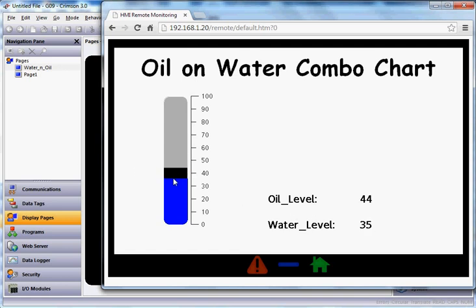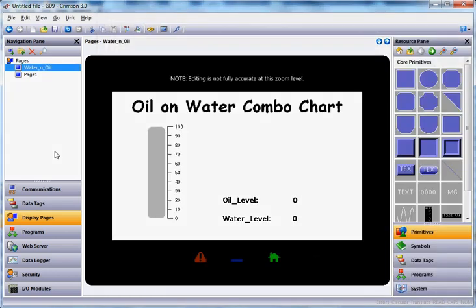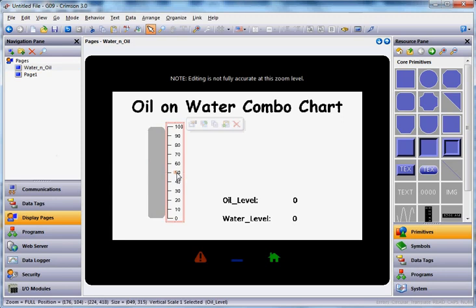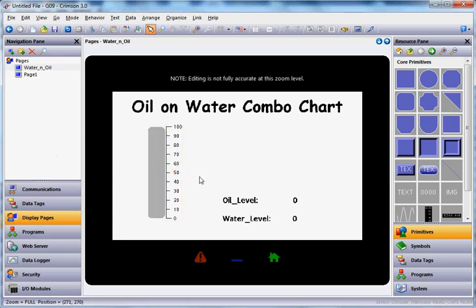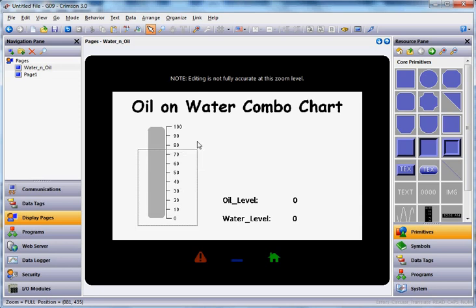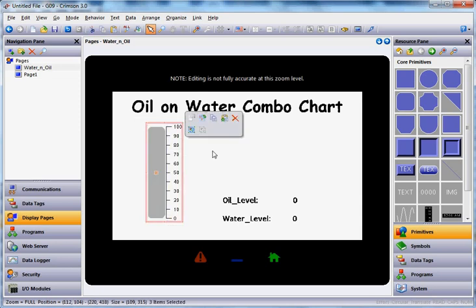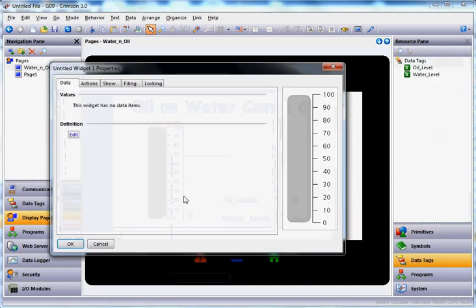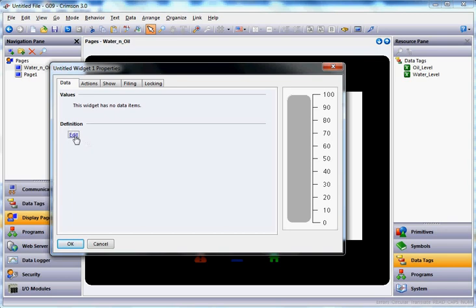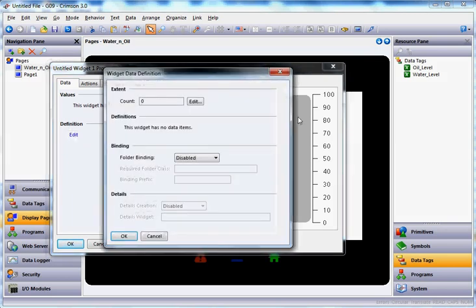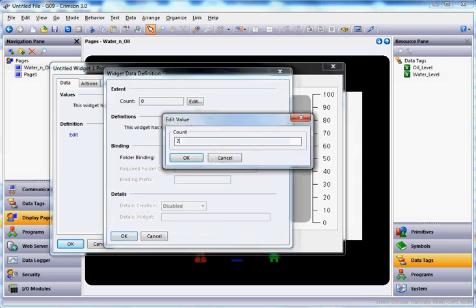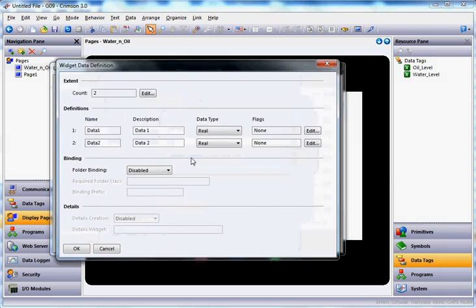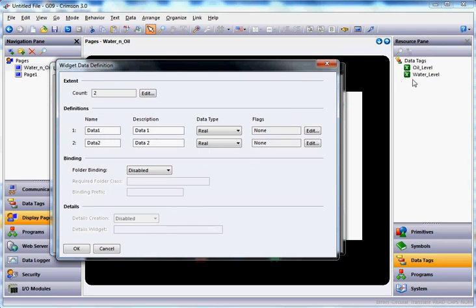Now if you want to save this as a widget that you can reuse over and over again, the easy way to do that guys is to, I'll go back here to crimson and if I say, if I take this and just move it over a little bit like this, if you take your mouse and some of you may have watched my widget videos but I'll show you how to make this a widget. If you take your mouse and simply go ahead and encapsulate all of this stuff, so you want to get everything together like that. Once you get it all together, you notice I got the red border on here, right click on this thing and come down to the bottom and click on widgetize. On the widgetize, now what we're going to do is define some widget items and right here where it says definition edit, hit the edit button right here. Here, this widget essentially just has two items, these two levels, so I'll hit edit and I'll say the count is going to be two, hit enter.